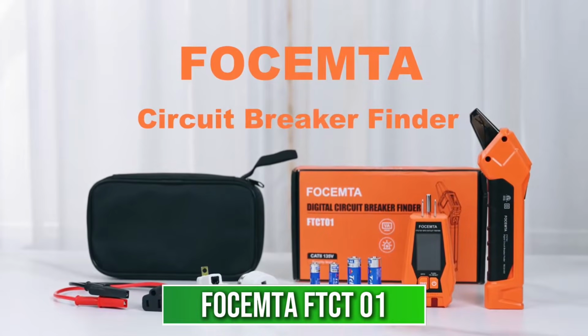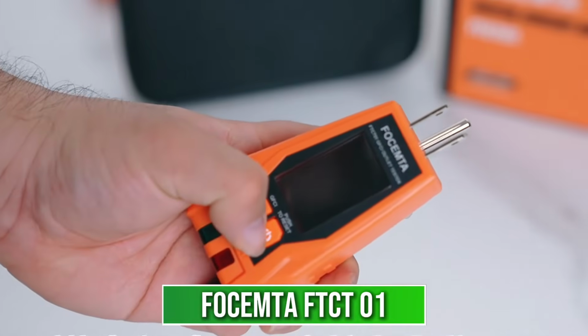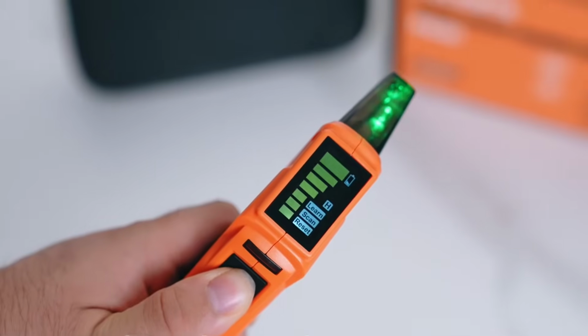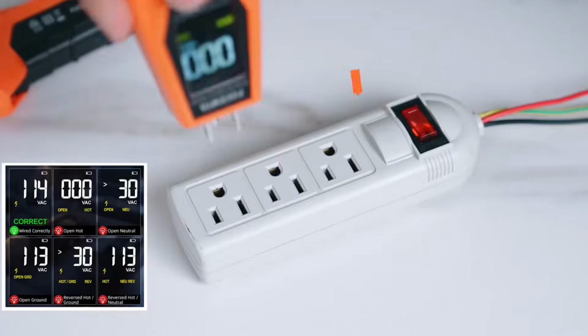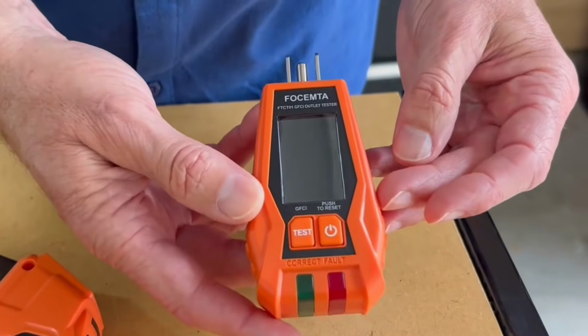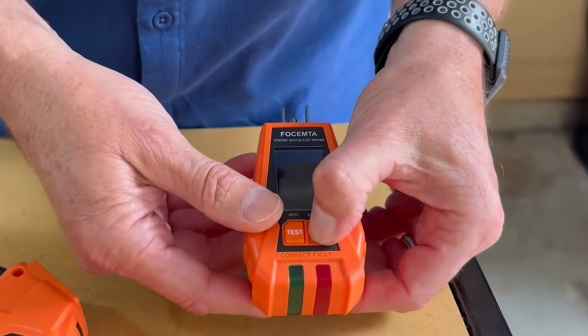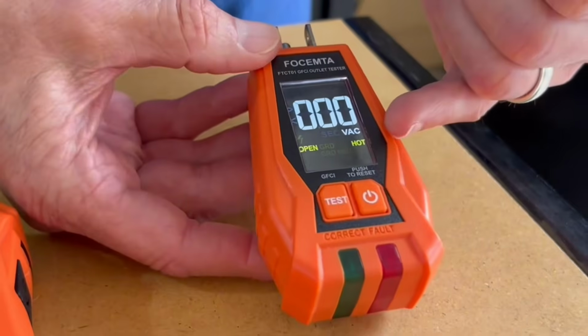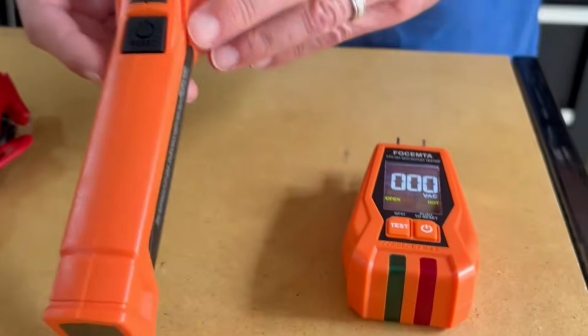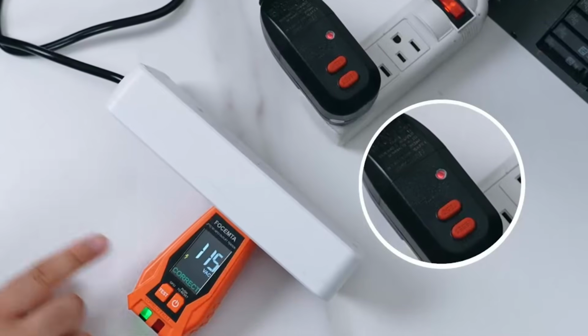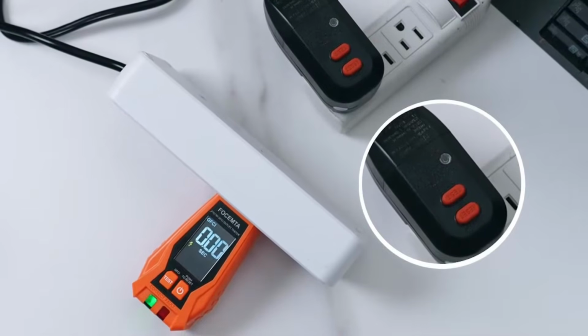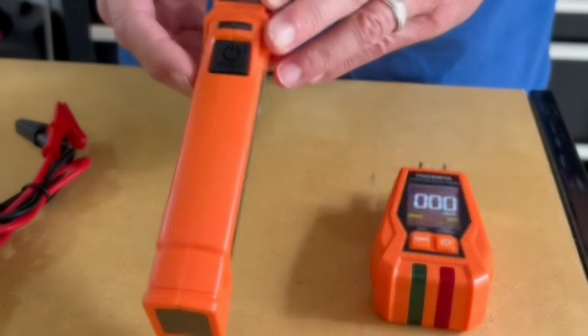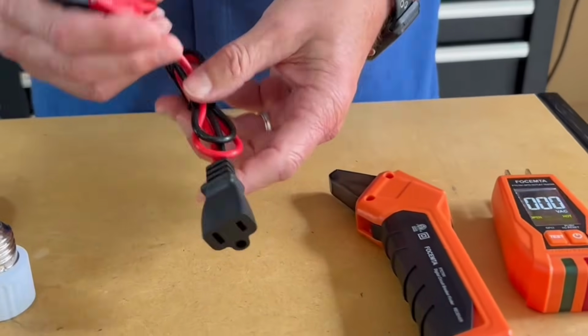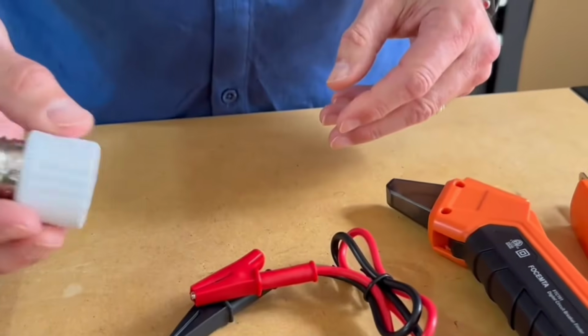The FOCEMTA FTCT01 brings something truly unique to the table, a 10-second data lock function. Here's why that matters: when you're testing a GFCI outlet and the circuit trips, the power dies instantly and your screen goes black. With the FOCEMTA, a built-in backup battery keeps the test data displayed on the LCD for 10 full seconds after the power cuts out, so you can actually read your fault codes in peace. It diagnoses 6 common wiring faults and even shows you how long the test ran.